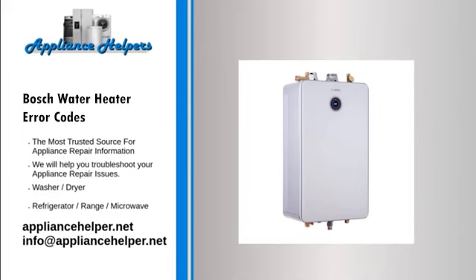Code CA. Problem. Excessive water flow. Fix. Make sure that the water pressure is less than 150 psi and the flow rate below 10 GPM. Check the wire connections on the water valve and control panel.